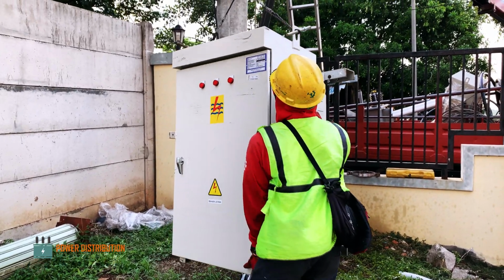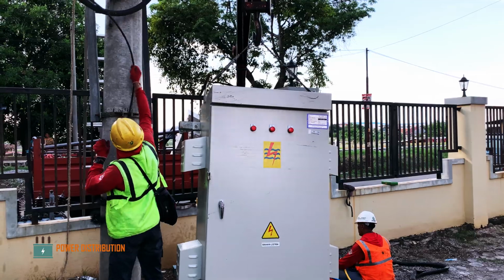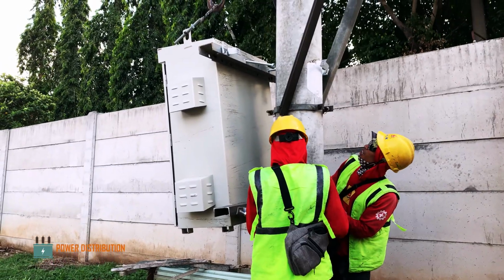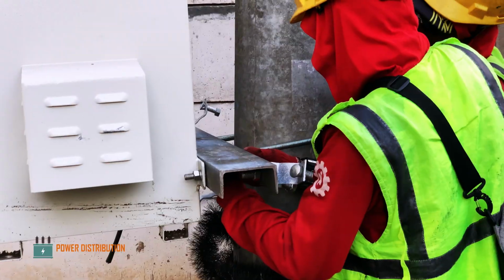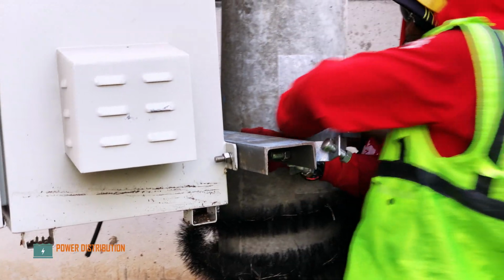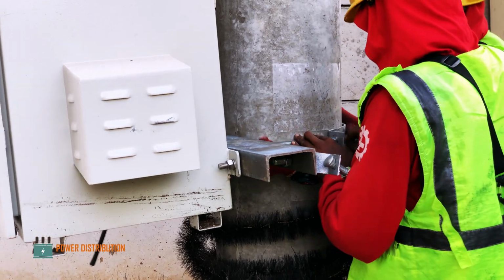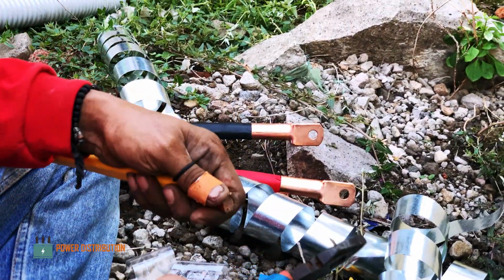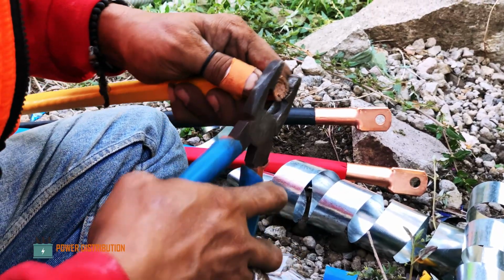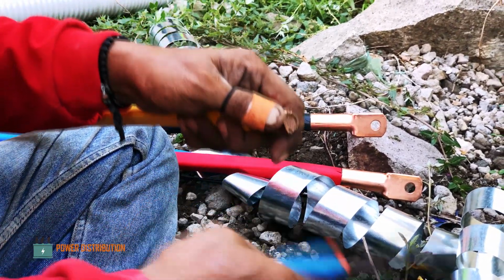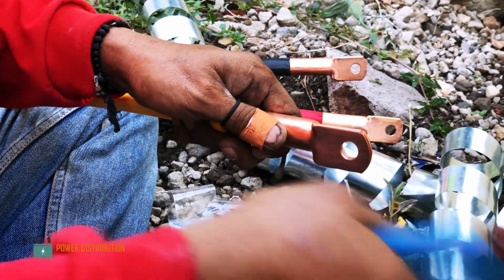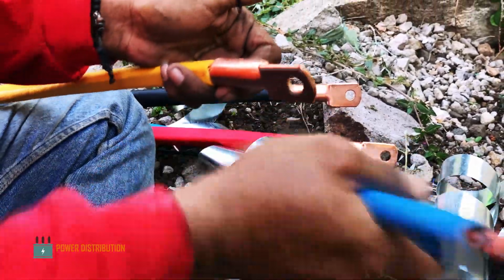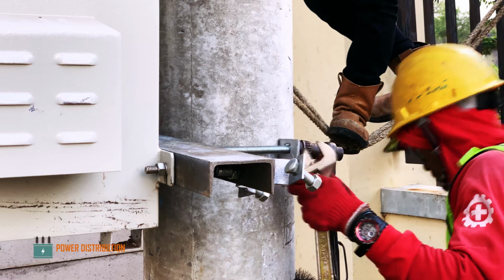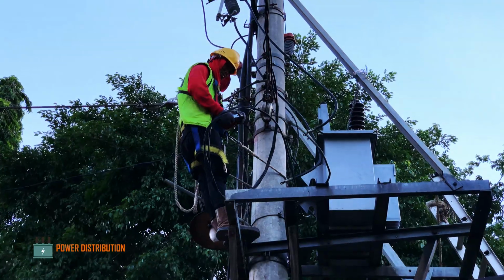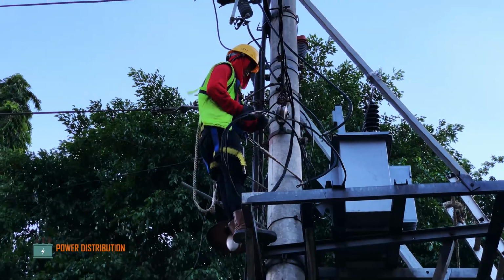Now the crew is ready to install the box onto the pole. They secure the box into the pole with 22mm threaded bolts. Meanwhile, the other crew install the cable shoes into the tip of the main 150mm squared distribution cable, which will be connected to the secondary bushing of the transformer. The lineman cuts the secondary distribution wire.